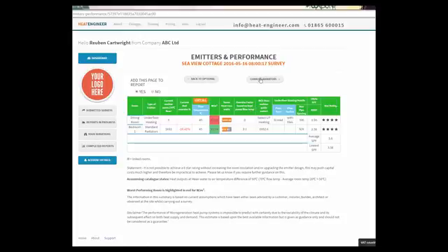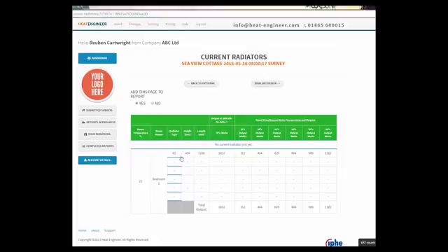If we go to current radiators, there's the K2 that we selected, and there's the output at a delta T of 50, and we've got all the flow temperatures with the outputs at those corresponding flow temperatures, which is a nice reference, so you can just double check what readings you're getting from that radiator. Yes, we want to include it in the report.